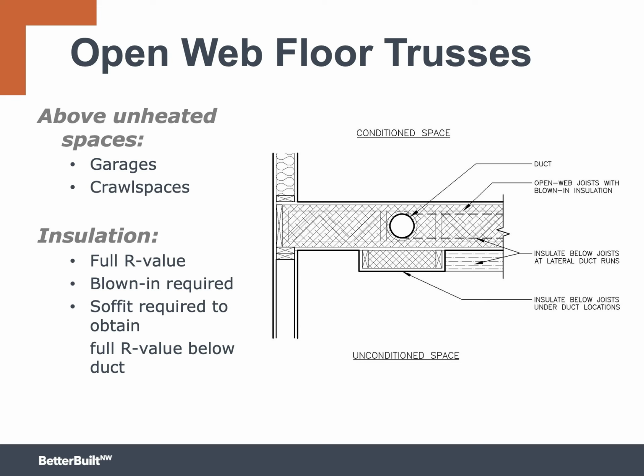Another possibility would be to use a rectangular duct that leaves several inches of space for rigid insulation that would achieve essentially the same insulating value as the floor cavity. For example, if you used polyisocyanurate insulation, which is about R6.8 per inch, you'd need 5.5 inches to reach R38, which is the standard floor insulation level. So in a 14-inch truss, that would leave about 8 inches for a rectangular duct. If that duct is big enough for that branch, it would work out. You'd have to figure all this out with the HVAC contractor to make sure that you've got the right size duct in a rectangular shape and can get enough rigid insulation below that.